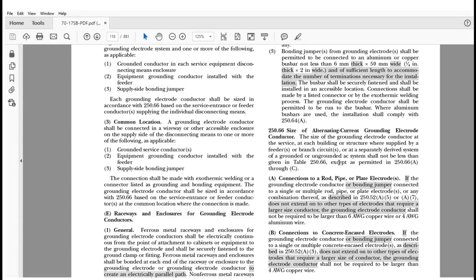All right. So if you read it, this is what it says down here: it has added the term bonding jumper, which is the proper term when you're connecting, let's say, a rod to a rod. If you're having to do the 25 ohms and you can't prove otherwise, you put in 2 rods. If you can prove 25 ohms or less, you only need 1 rod. Then the bonding jumper is what connects those together. And they do not have to be larger than what 250.66(A) is calling for here, which is not required to be larger than a 6 AWG copper or 4 AWG aluminum wire.